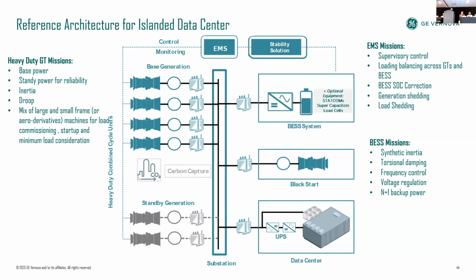So we can have two kinds of design. In one, we use the BESS or the STATCOM solutions to fully mitigate the fluctuations, where the size will be larger because we have to fully compensate the load. The other is where we allow the BESS to act based on the frequency change, and that will count on the fact that the synchronous system inertia will also help support some of those transients, right?